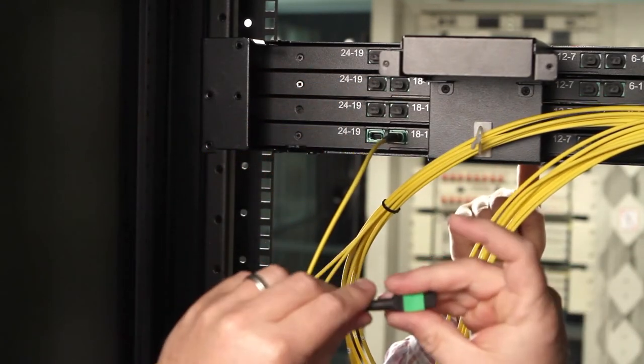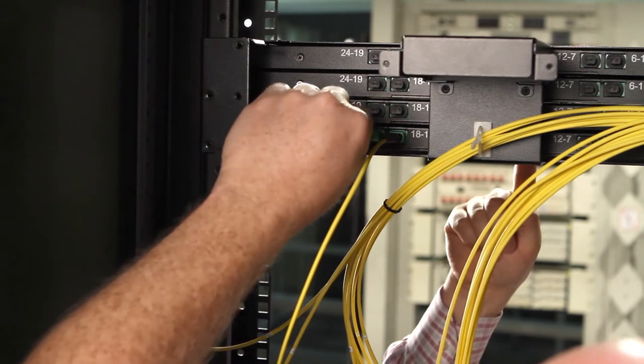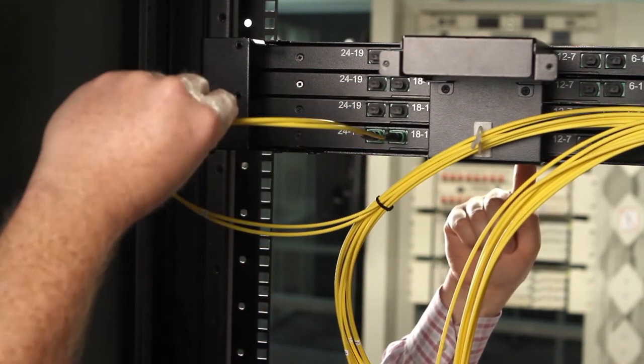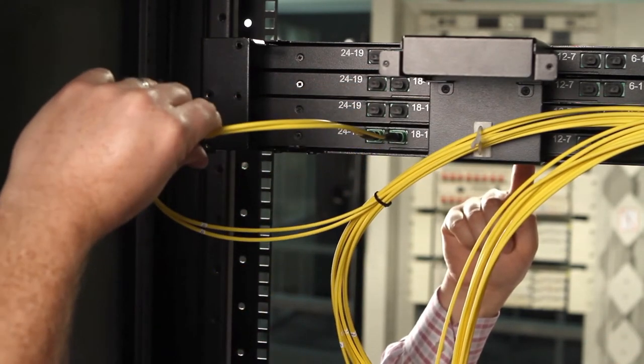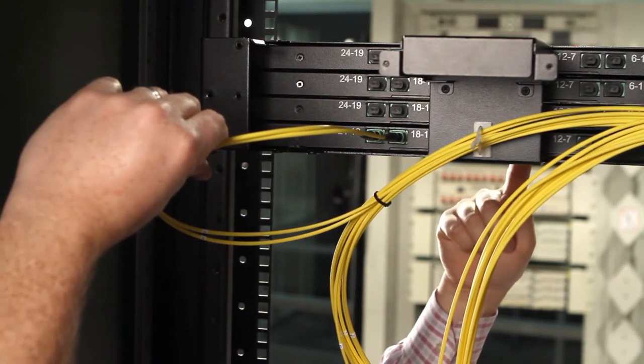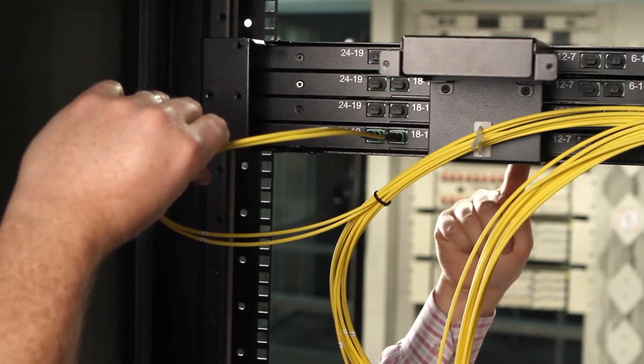Tail 16 will go in the other MPO on the other side. The blades are keyed down. If the MPO key is up, you can just twist the MPO 180 degrees and insert it.